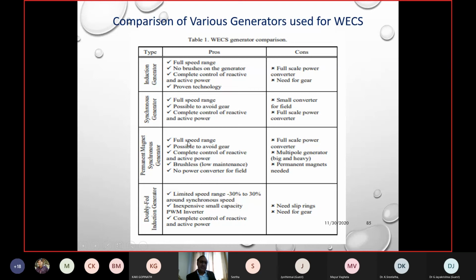Then permanent magnet synchronous generator: full speed range, possible to avoid gear, complete control of reactive and active power, brushless, low maintenance, no field winding is required, no power converter for the field is required. Cons: full scale power converter is required, multipole generator, big and heavy, permanent magnets needed.